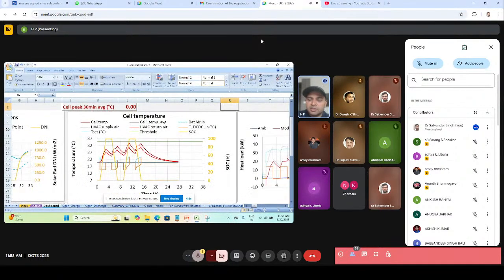Batteries don't always generate the same heat—they generate less heat when new, and as they grow older, their heat generation starts rising. So when designing, we always design for the worst conditions: what will happen at end of life, at 50 degrees C ambient, when it's raining, or near a seashore where salinity can corrode or erode the thermal components.